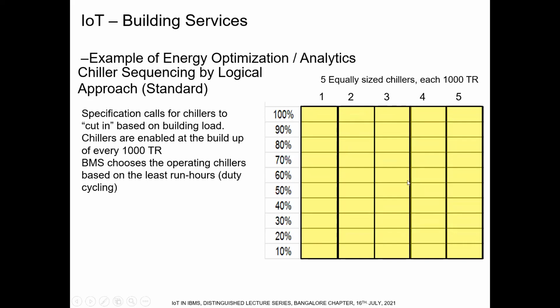This chiller number 1, 2, 3, 4, 5 is decided based on what is called runtime totalization. It calculates the amount of run hours by each chiller, and the next chiller that cuts in will be the chiller that has operated the fewest hours, so that duty is shared amongst all these 5 chillers. At the end of 4 or 5 years, you will see approximately the number of hours run by each chiller is the same. So you get a fair amount of extended life with the standard type of automation that is provided by the BMS.